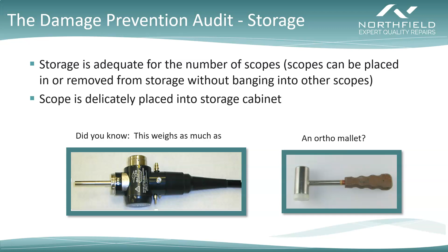Now, one key piece of preventing damage is something that gets overlooked by administrators very frequently, and that's ensuring that there's an adequate number of scopes for the number of procedures that are being performed. Flexible endoscopes are expensive, and so sometimes administrators will try to get by on as few as possible. And we see this coming up very frequently. In fact, there was a survey conducted by Ofstead and Associates in Iowa that found that 70% of reprocessing technicians feel that they are under pressure to go faster when they are reprocessing scopes.